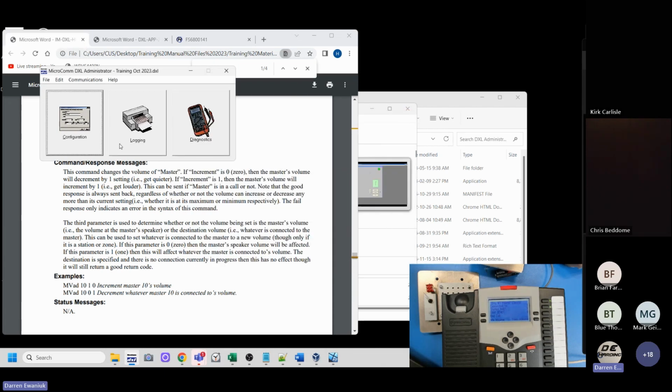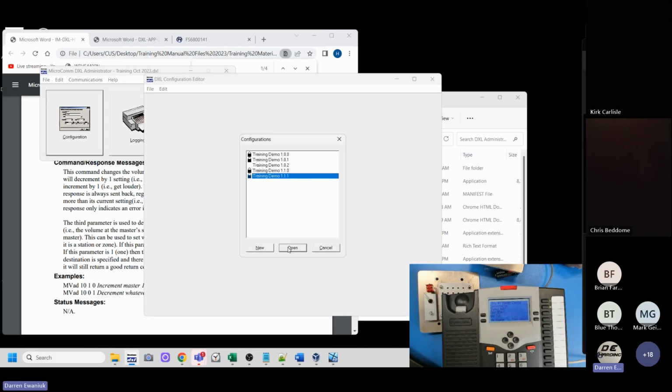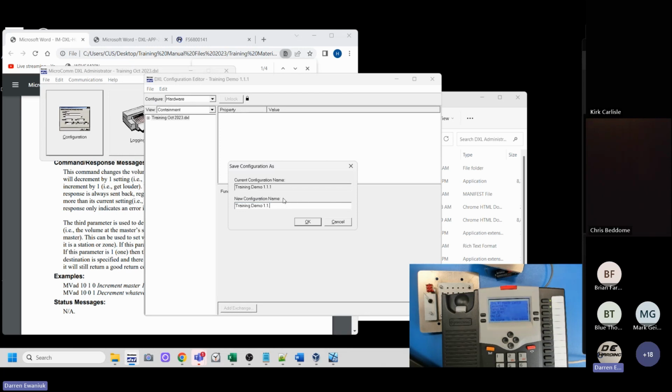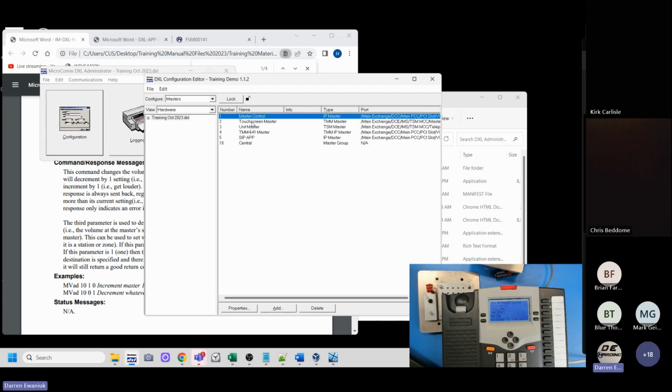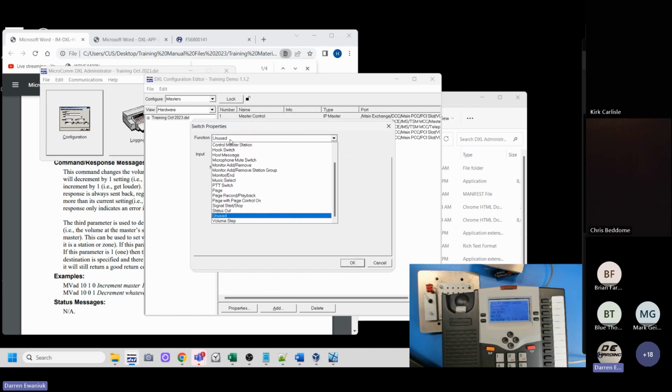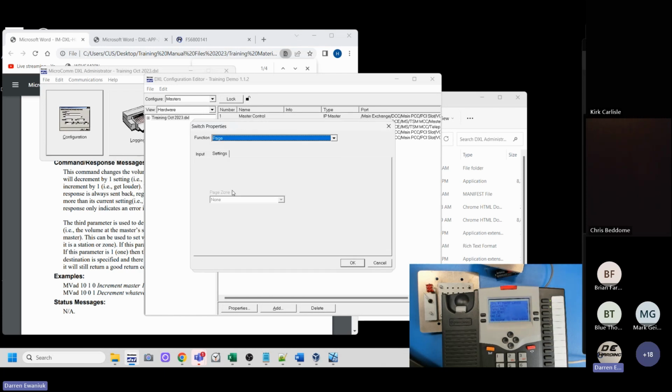if I go back into the switches here, I'm going to save it again as Master control 1, switches. So I could do a page switch and pick which page zone, though I don't have a page zone. But further information on this input tab: this contact type, momentary, means you press and release it and it does something until you press and release it again.